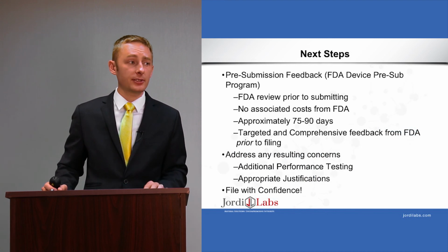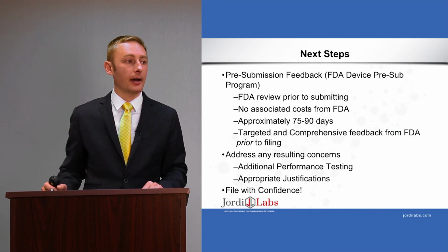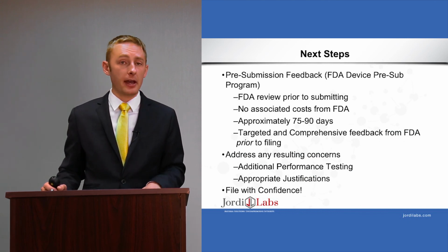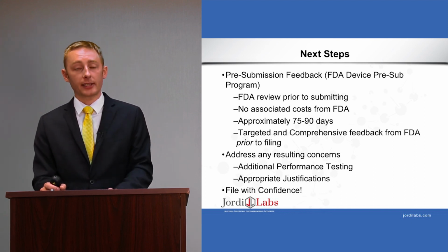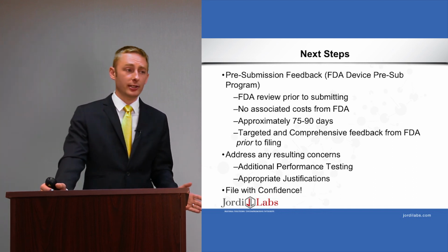So the next steps for this, the FDA has a pre-submission feedback process where the FDA reviews your submission before you technically submit. There's no associated cost with the FDA.